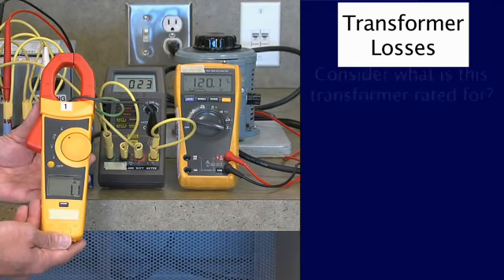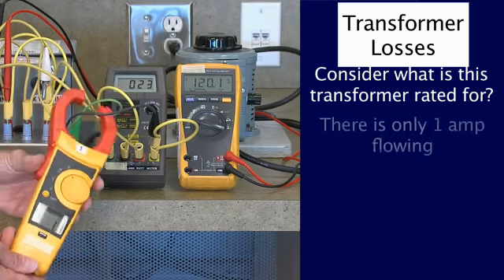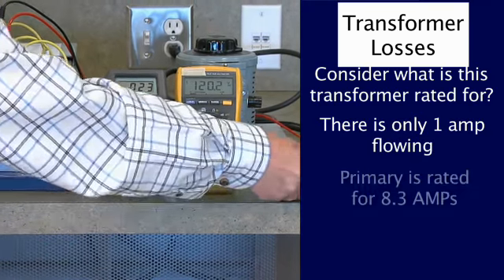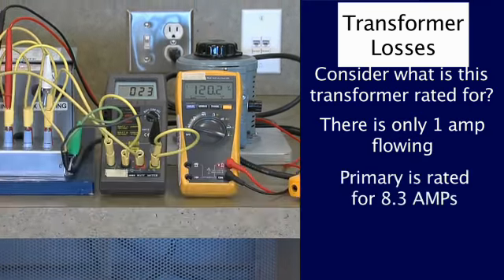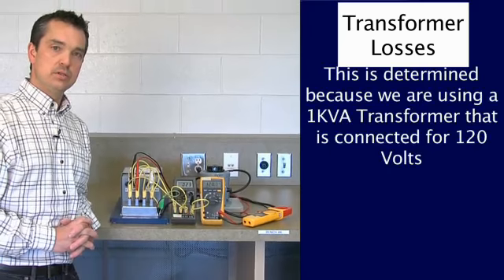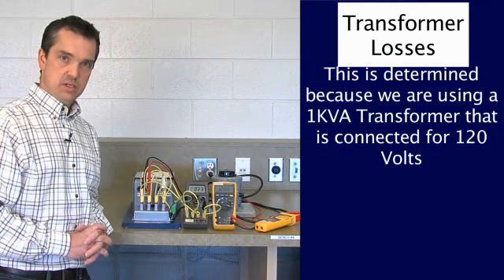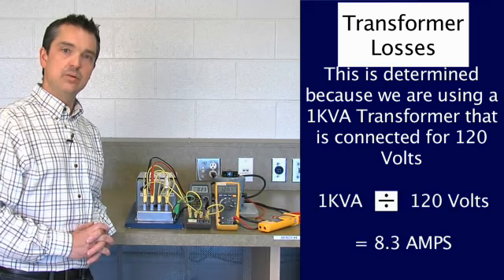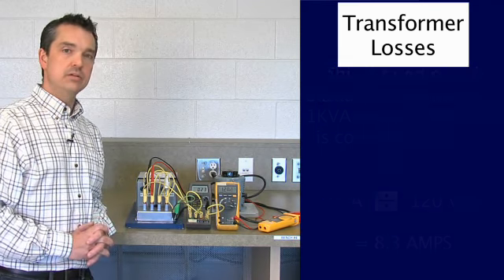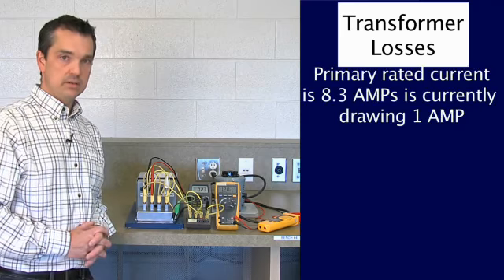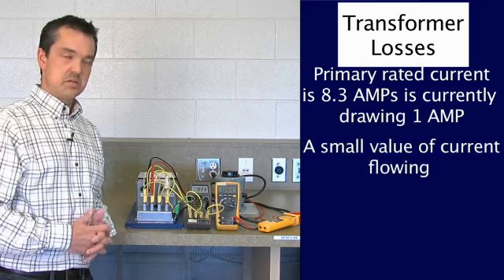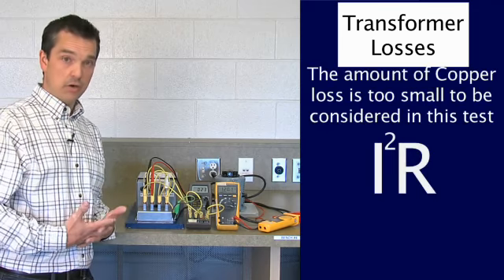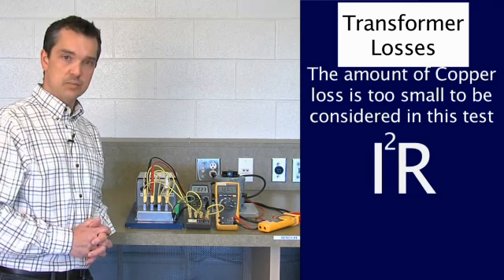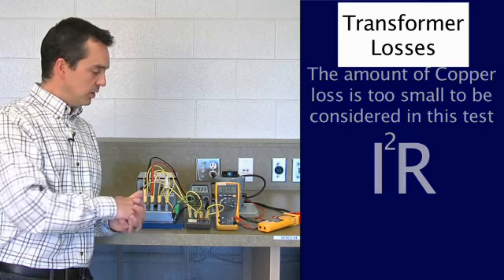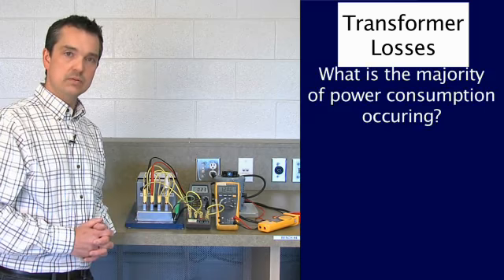And that 1 amp, we need to consider, what is this transformer rated for? There's only 1 amp flowing right now. So if there's only 1 amp flowing, well, my primary happens to be rated for 8.3 amps. And where that comes from is it's a 1 kVA transformer that is connected for 120 volts. 1 kVA divided by 120 volts is equal to 8.3 amps. So my primary rated current is 8.3. I'm only drawing 1. It's a very small value of current flowing. So is there a little bit of power loss there of I squared R, of copper loss? Yes, there is, but it's very small and it's insignificant to the test. So what is the vast majority of power consumption occurring here? It's in the core.